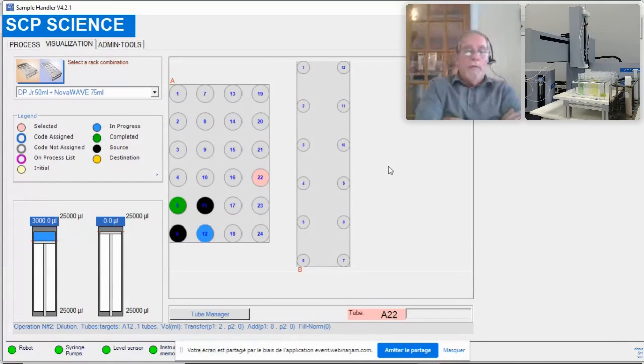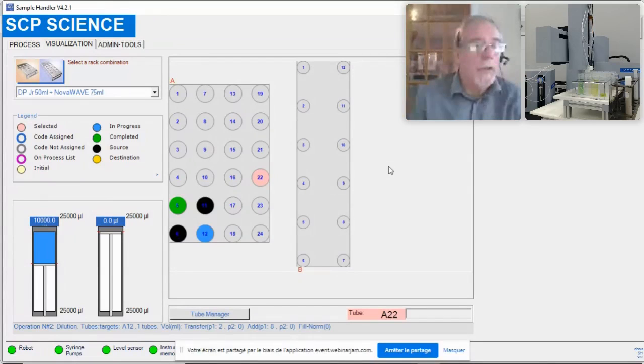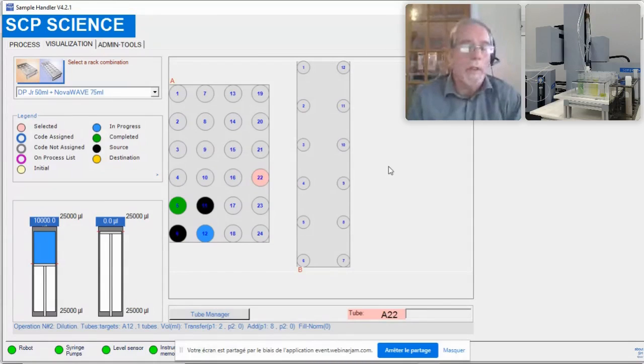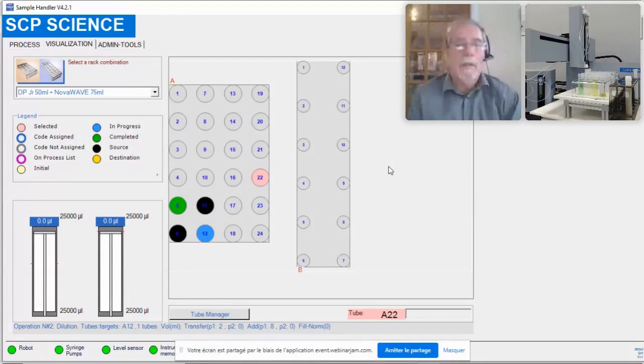So we're going to do the reverse here, where we're going to come to the tube here, and we picked up the diluent. Now we're going to go down to the bottom of the digitube. We're going to turn the bubble stirring on to mix the sample. You can see the bubbles in the sample. Then once it's bubble stirring for 7 seconds, we'll then pick up our aliquot of our sample. So with the 25 mil syringe, it's possible to pick up as small as 0.05 milliliters, so 50 microliters accurately, to do a dilution. So you can do a 50 microliter to a 10 milliliter dilution with good precision, with better than 2% accuracy.